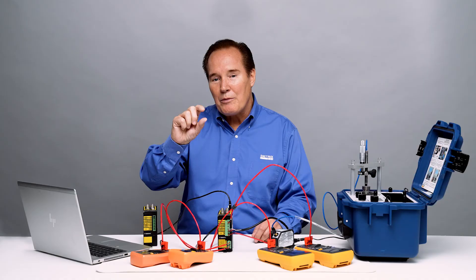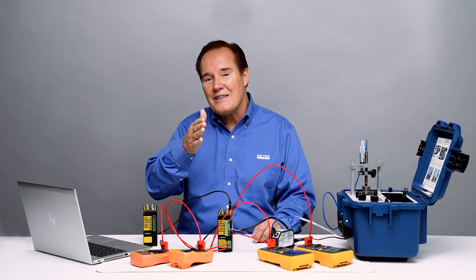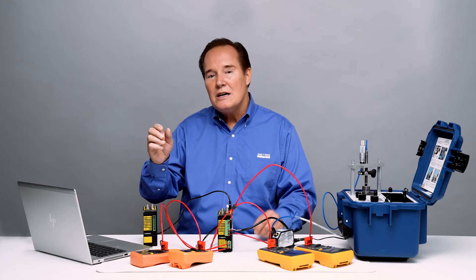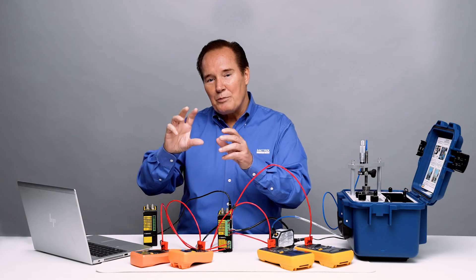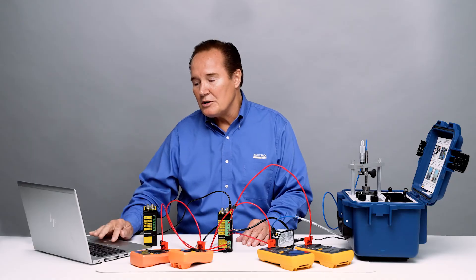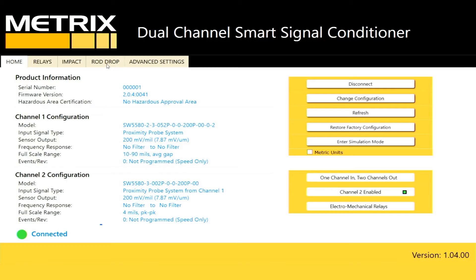The trick to rod drop is we don't want to just see the position change where we measure. We want to extend that using similar triangles to where we see the actual piston rod or the piston change within the cylinder, and we want to see the rider band wear. So that's what we're going to do in this exercise, and we're going to do that with our software.